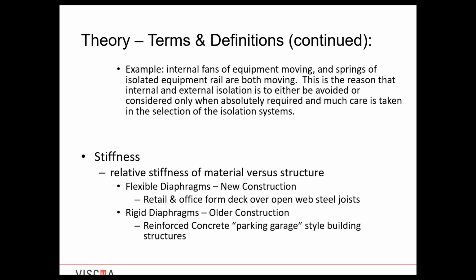So this really becomes a reason why internal and external isolation is either to be avoided or considered only when absolutely required. And much care has to be taken in the selection of the isolation systems when you have a 2 degree of freedom system. So typically on that slide with the nice 4 spring isolators as visual aids, in that bottom left corner with the sheet metal curb, or in the bottom right corner with the concrete inertia base with the springs, equipment that would be bearing on that would not have internal isolation.